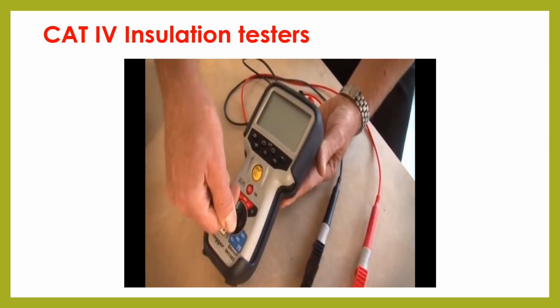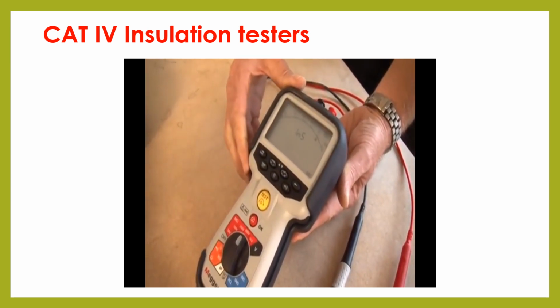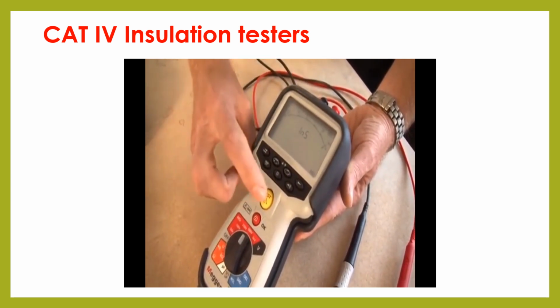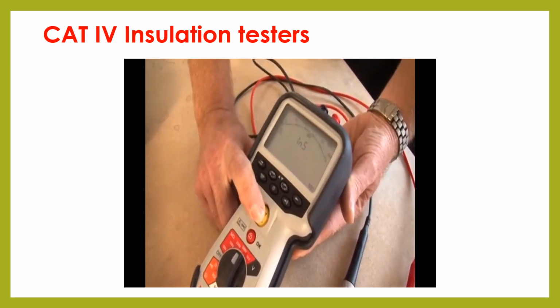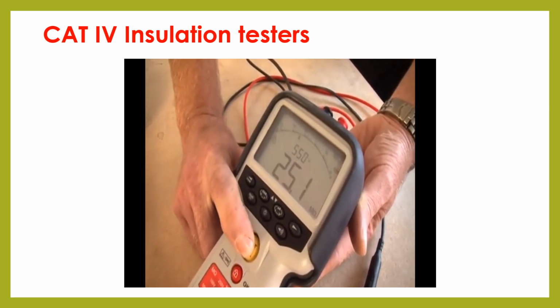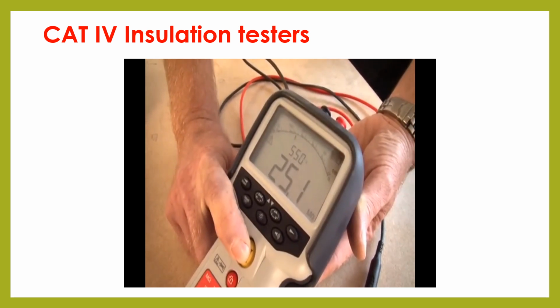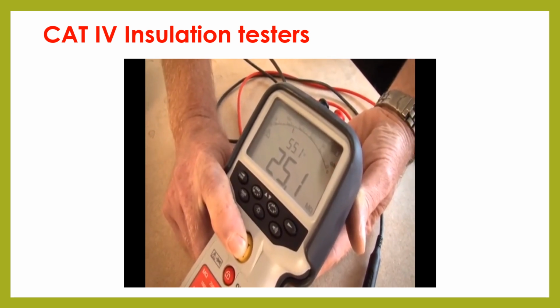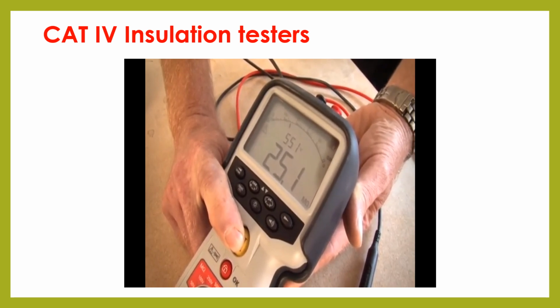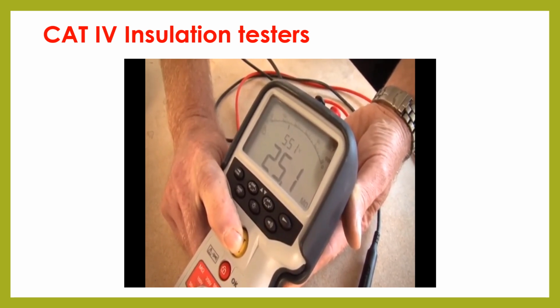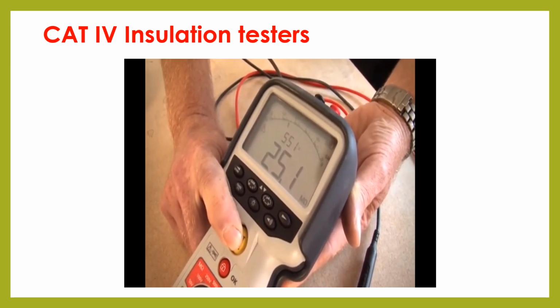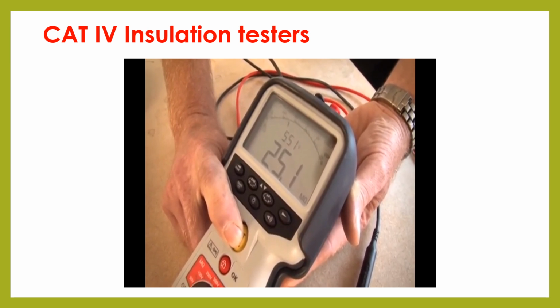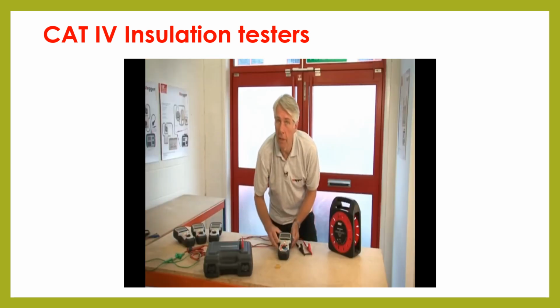In this case, I'm going to select 500 volts and then simply press and hold the test button. And you can see displayed there the reading of 25.1 megohms, both digital and on the analog arc, and then above it a reading of 551 volts, and that is the actual test voltage. Okay, so that was the insulation test.